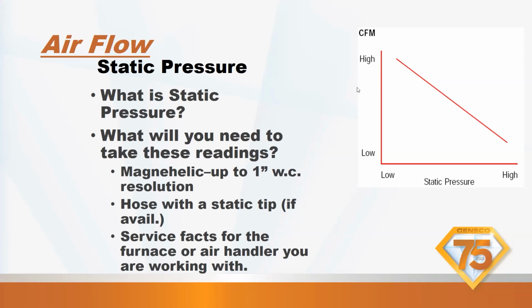So we can take the total static through the coil, or we could take it through the gas furnace itself. Both of those components have static pressure charts inside of the book, service facts, and we can calculate our static pressure that way. On an air handler, the air handlers have the same coil in them, okay? We don't change coils inside of air handlers. So if you have an air handler, you take the static pressure from the return to the supply, and that's how those charts are built, okay? You're going to need a magnehelic or a pressure tester that goes up to 1-inch water column, a hose with the static tips, service facts for the furnace or air handler you're working with, and then you take your measurements, go to the service facts, and look at the charts.